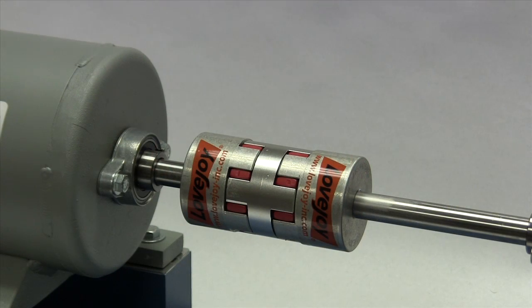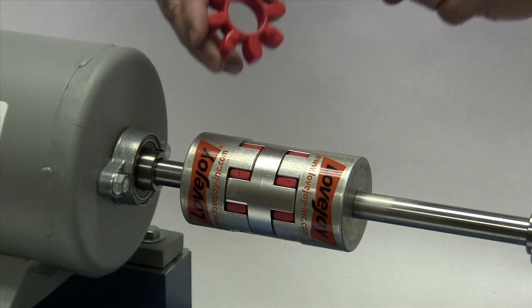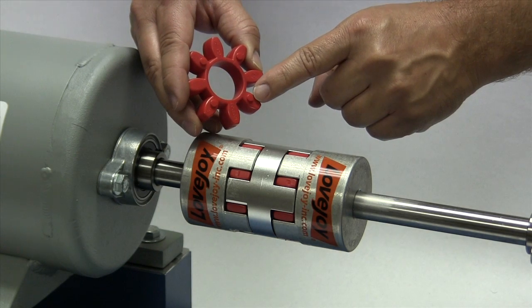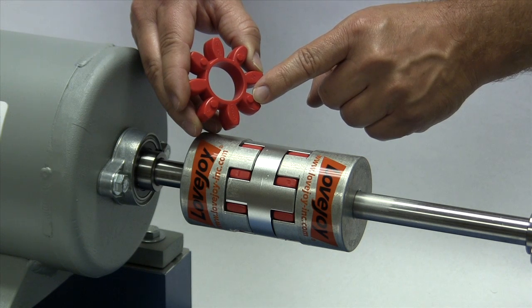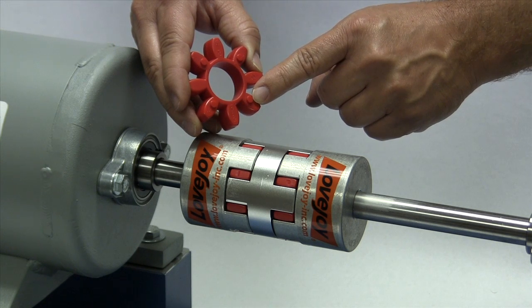Now we will carefully move the equipment into place, bringing the hubs together until they barely touch the raised dots on the sides of the spider. Care needs to be taken to ensure the jaws do not come into contact with the jaws of the opposing hub as we move the equipment.